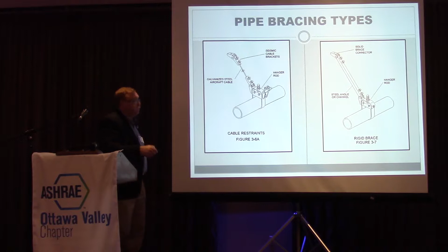Pipe ductility decides the performance of the piping system. If you've got a glass pipe, that obviously isn't going to be as strong as a welded steel pipe. So in the US code we have this Rp value, which is in the bottom of our code equation. The higher the number on the bottom, the lower the force you have to design for. So if you've got steel or welded pipe, the Rp is 9, which cuts the force down by 9.